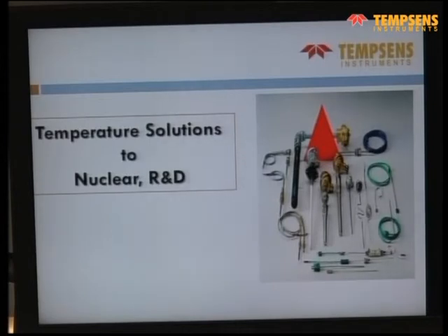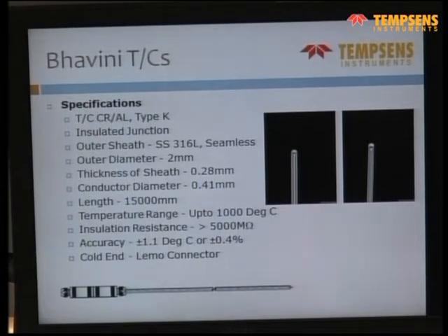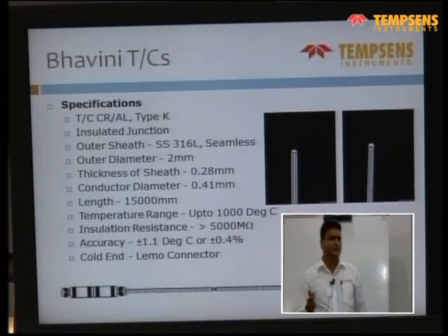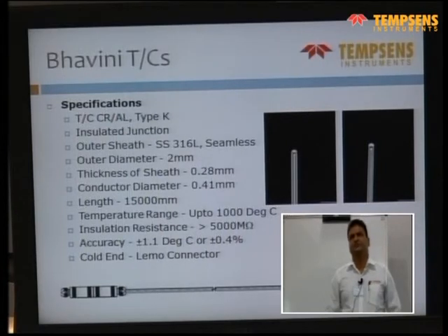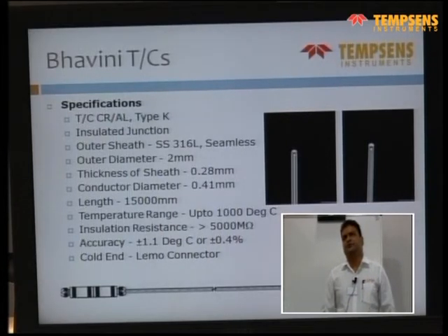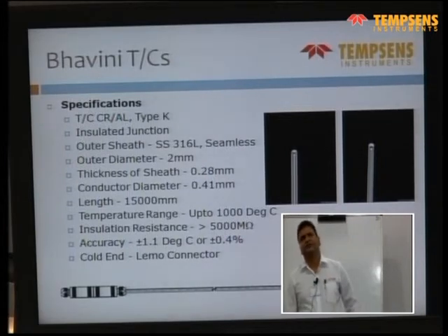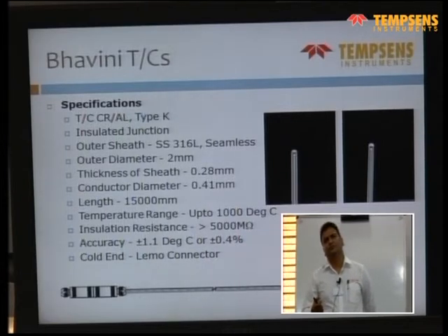We work with a lot of nuclear and R&D projects like NPCIL, BARC, Bhavini and other DRDO and other facilities. For example, this one we did with Bhavini, we supplied over 1,500 sensors. Each of these sensors was 2 millimeter diameter, for taking the temperature of the sodium pipes which are running throughout the plant. It was as per ASTM E235, which is a special standard for high reliability and nuclear application. Each sensor was supplied with more than 5,000 mega ohm insulation resistance.